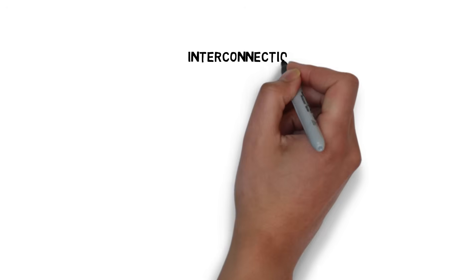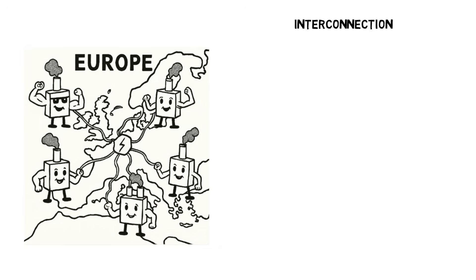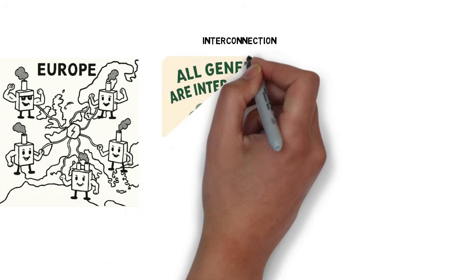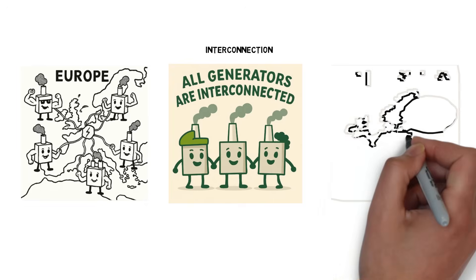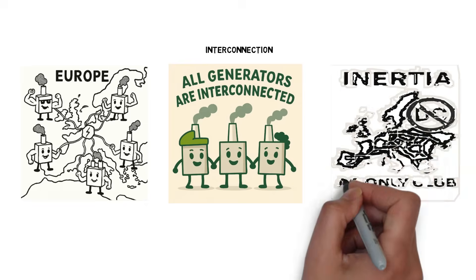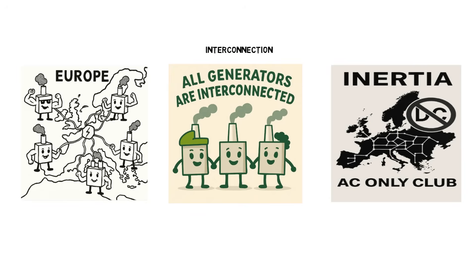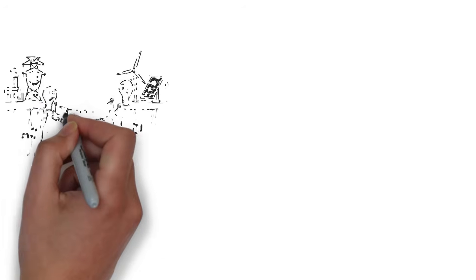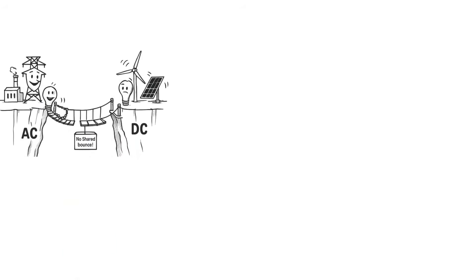Europe's power grid is a vast web of interconnections. Some countries are tightly woven into it, others less so. These links can be used to tap into the inertia of neighboring grids, borrowing stability when needed. But there's a catch. The benefit depends on the size of the interconnectors, and whether they're AC or DC. If the connection is DC, it's electrically decoupled. That means no shared inertia, no stabilizing force.